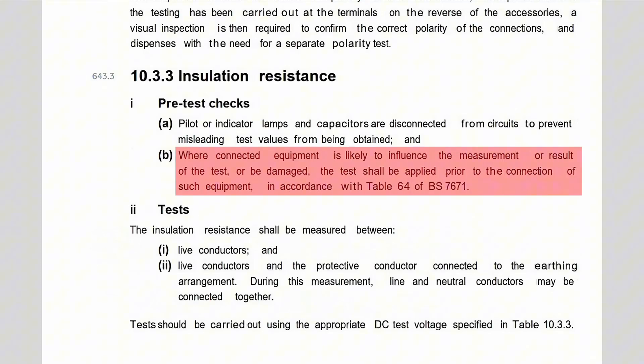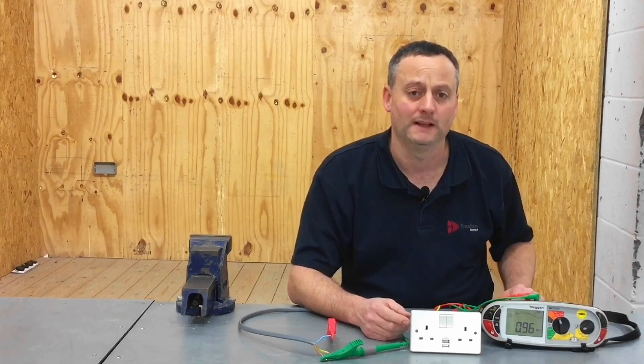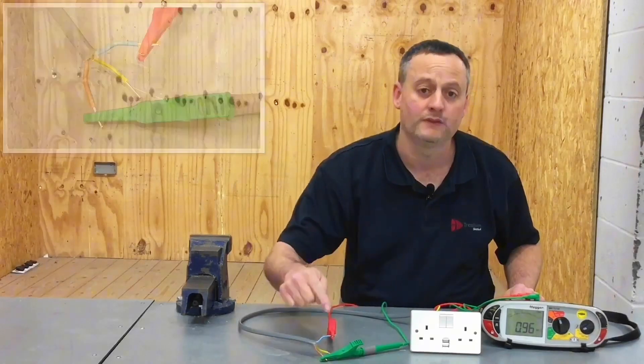Manufacturers say we cannot test at 500 volts because we will destroy the electronic components, and BS 7671 agrees. Therefore, if we want to protect those components, we should be testing at 250 volts. Let's see what reading we get on insulation resistance at 250 volts when testing between live conductors.